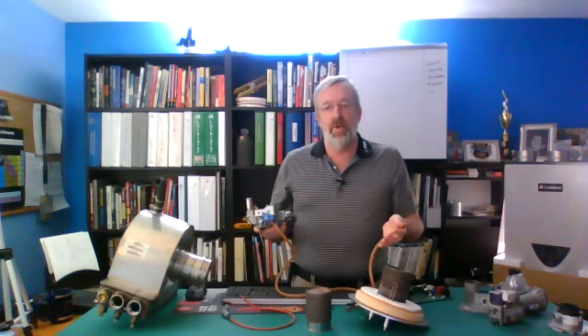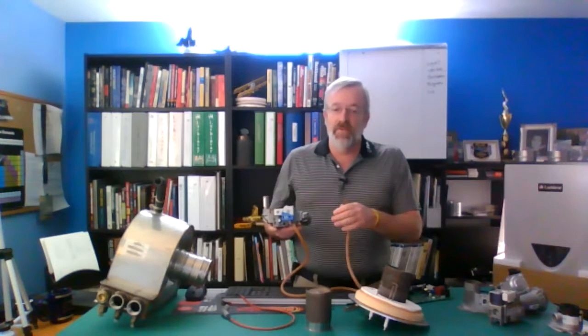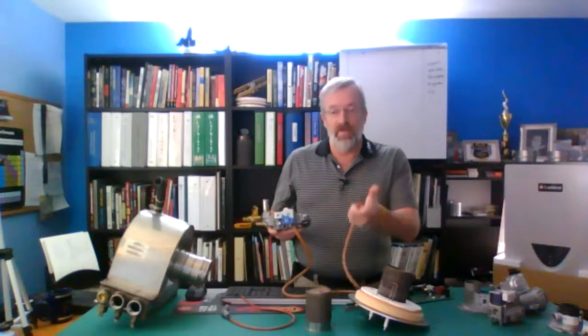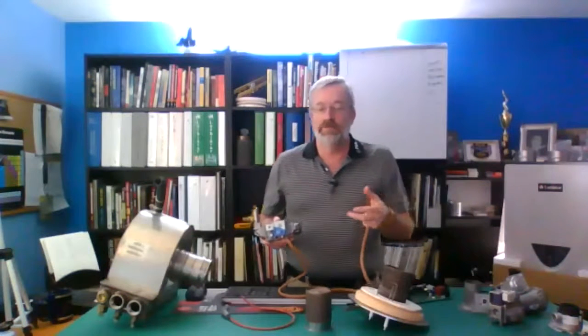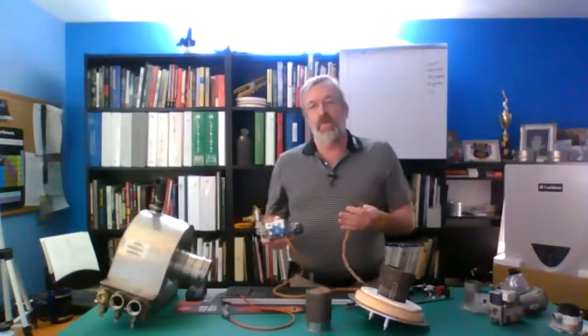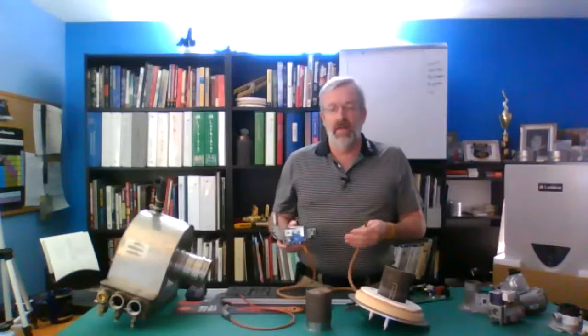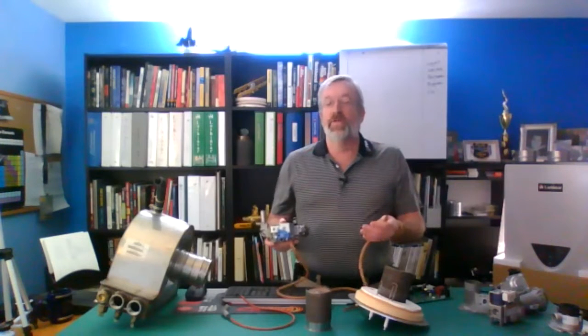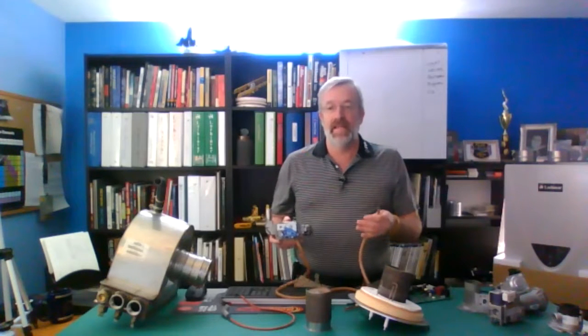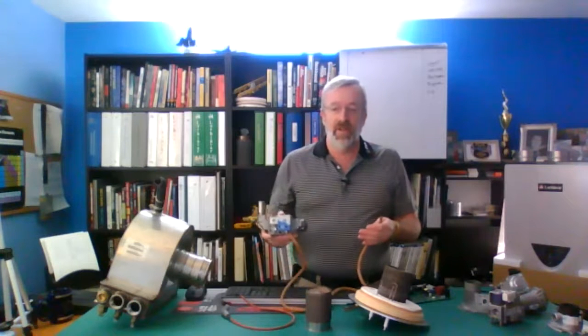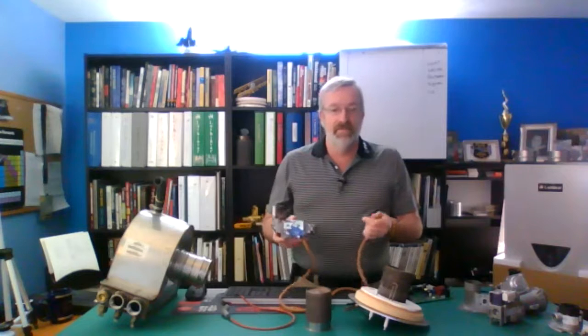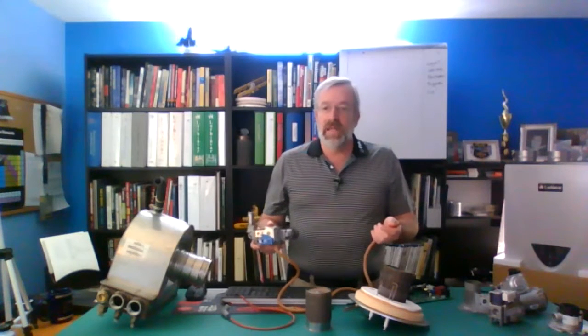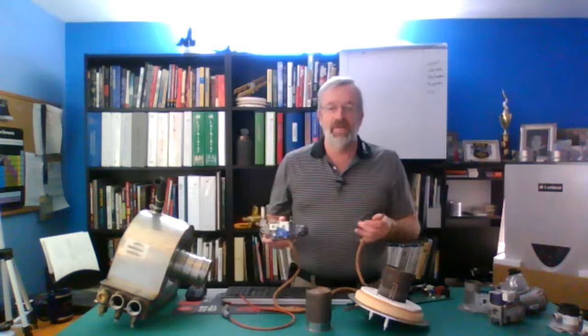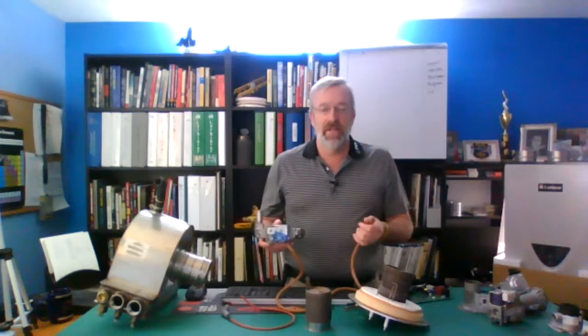Now I want to cycle my boiler through. So what I'm looking for is, do I have gas volume? Do I have gas pressure? And does my gas valve open? So how do I tell that? Once I put my manometer on there, really the first thing that I'm going to do is get my static pressure, and that is the gas pressure with the gas valve closed and the boiler off. So what I'm looking for there is somewhere between 4 and 14 inches. So let's just, for this example, say we have 8 inches of gas.